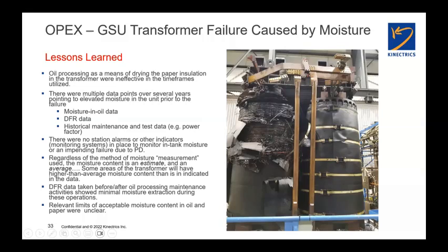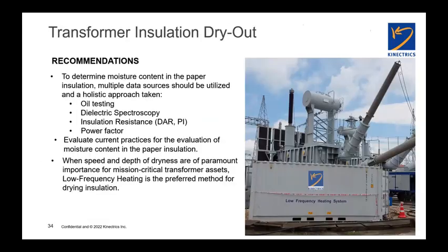I can guarantee you that in the 8 weeks before this transformer failed, they hooked up a ginormous oil processor, ran it for 7 or 8 days, and the water content instrument on that oil processor would have shown that the oil being circulated through the processor had a moisture content of probably around 2 parts per million. And they declared victory and moved on. The problem is that's the oil. We're interested in the paper. And by the way, they did do a dielectric spectroscopy, and it showed that after the oil processing, the transformer was still wet. I don't think the people involved knew the significance of those numbers, and had they known, they would have dealt with it.